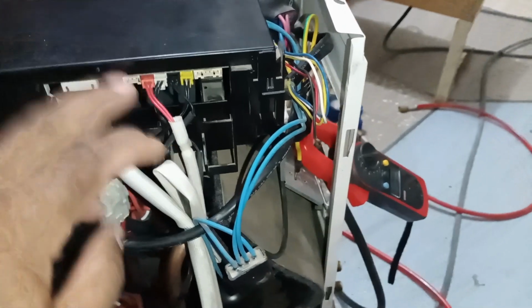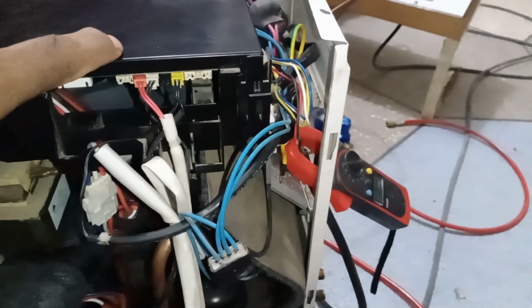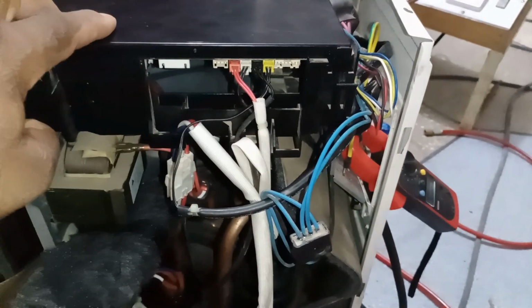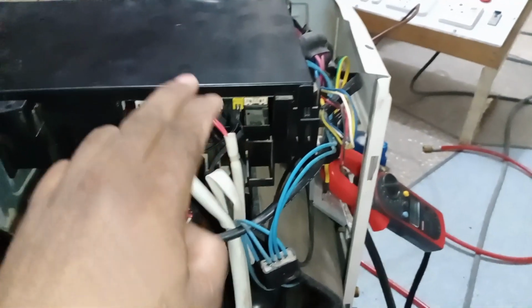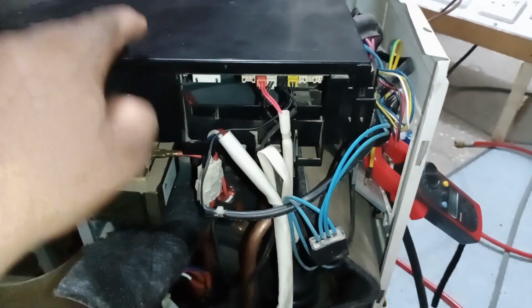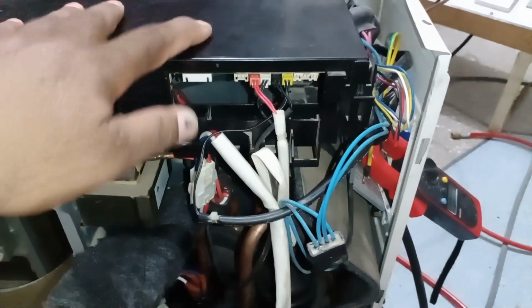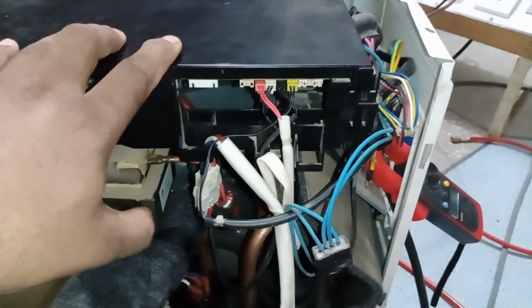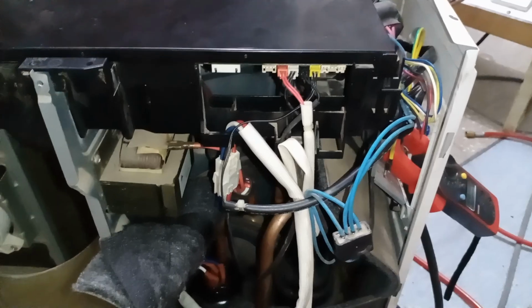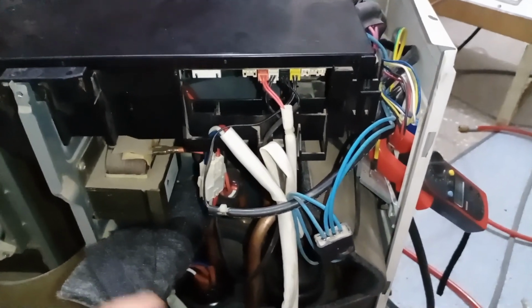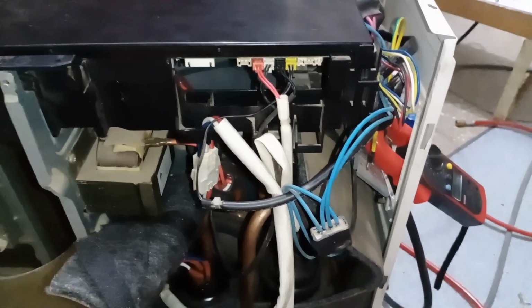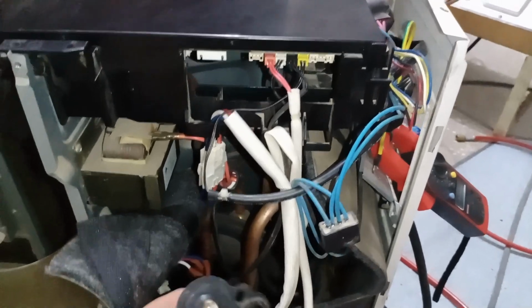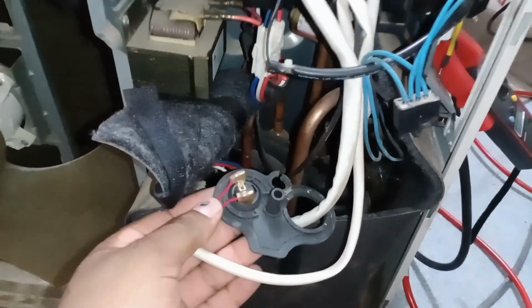How to fix error 15. 1. Check the connector. Ensure it is properly plugged in and secure. 2. Inspect the wiring. Look for any cut or damaged wires. 3. Test the thermostat. If it is faulty, replace it with a new one. 4. Check PCB continuity. If the circuit is not complete, repair any damaged connections. Once the faulty thermostat is replaced, the error 15 will disappear and the unit will return to normal working condition.